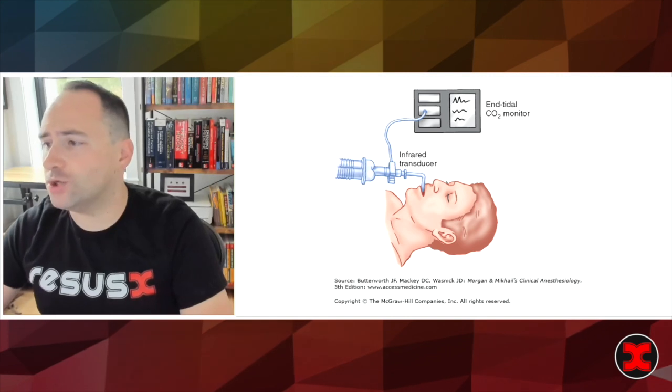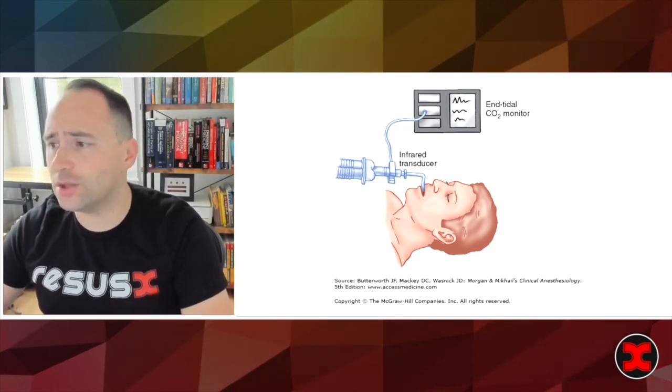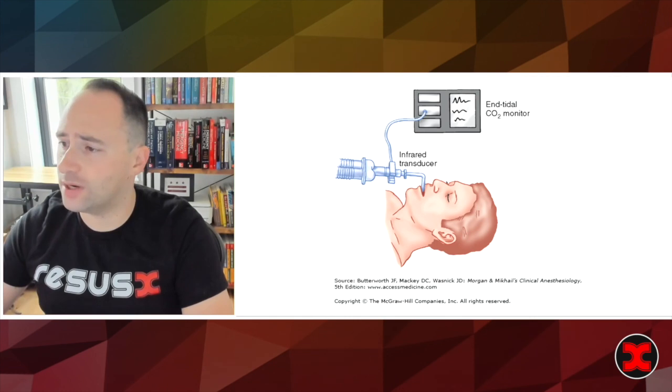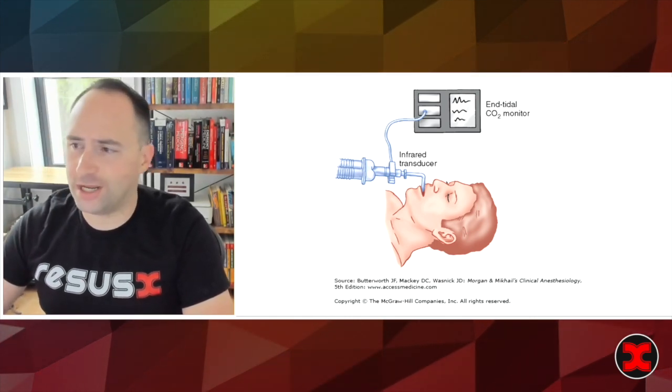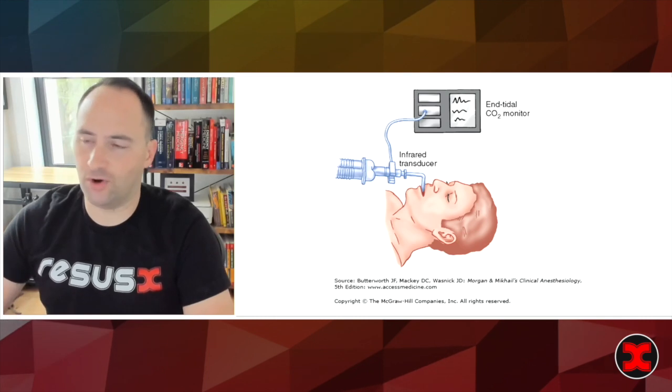Mainstream modules are connected very close to the endotracheal tube and it has an infrared transducer approximating the ET tube. There's a very small increase in dead space which is virtually forgettable.